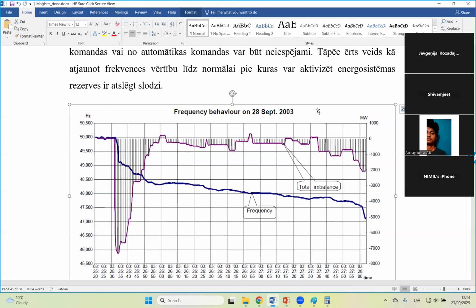N is the number of elements in the power system. And N-1 means the loss of any one element of the power system. So it means that if you lose any element of the power system, any line, any power generator, any substation, your power system will continue all its functions without any problem. So in this case, they lose one line, and as a result, there is overload of another line. So this means that N-1 is not true. So this is a fault of the system operator, because this operation mode is incorrect. This is the second problem.